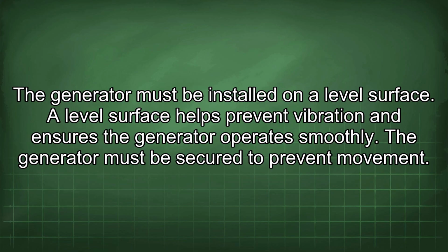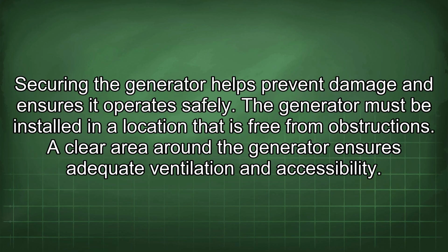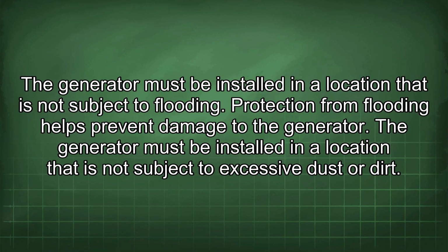The generator must be secured to prevent movement. Securing the generator helps prevent damage and ensures it operates safely. The generator must be installed in a location that is free from obstructions. A clear area around the generator ensures adequate ventilation and accessibility. The generator must be installed in a location that is not subject to flooding. Protection from flooding helps prevent damage to the generator.